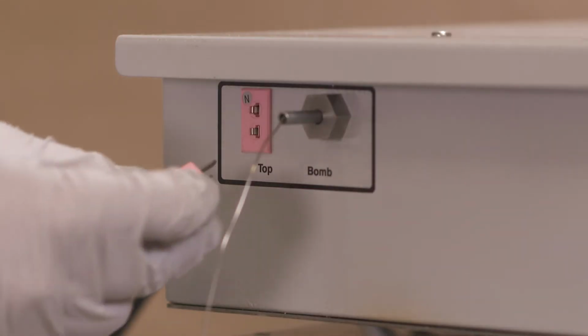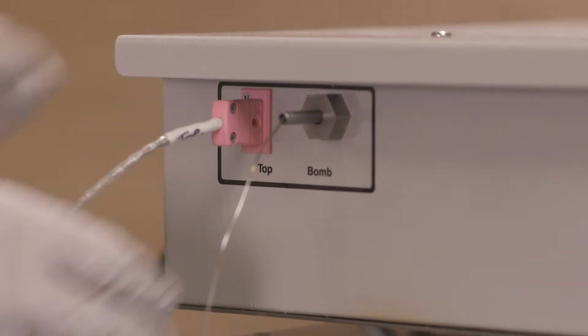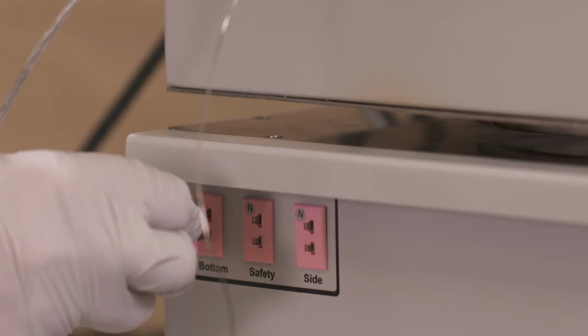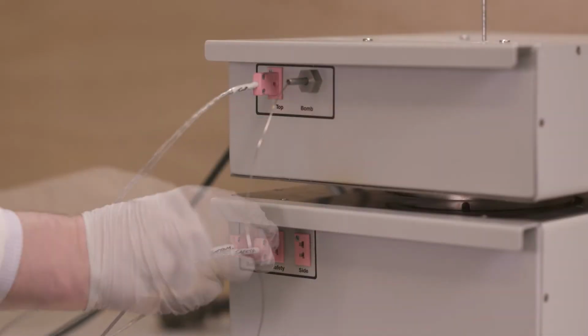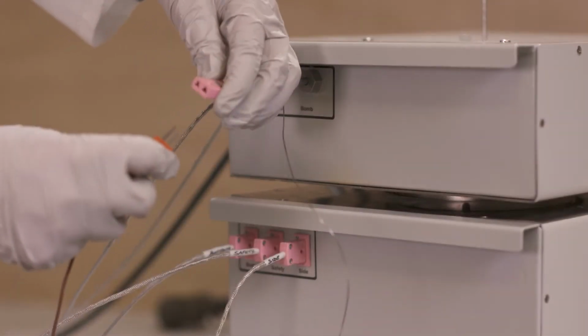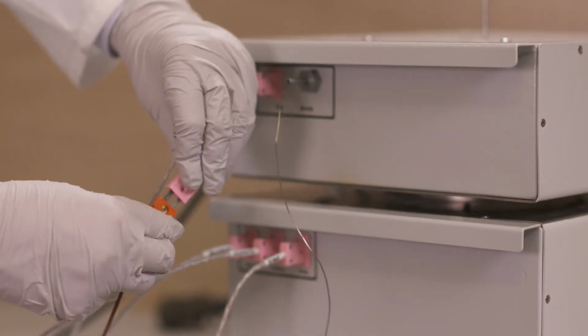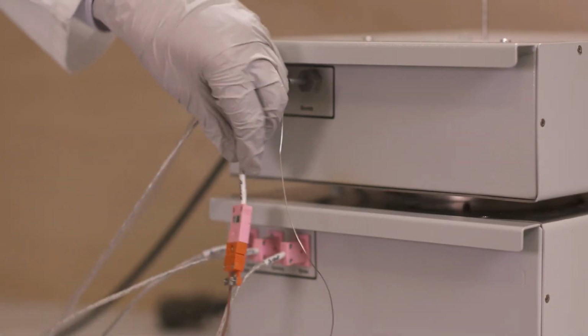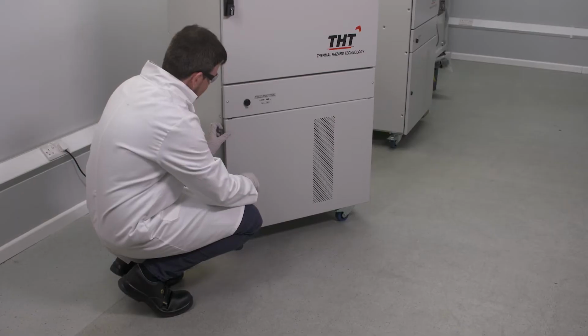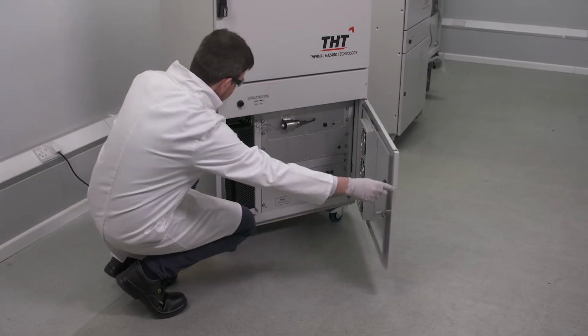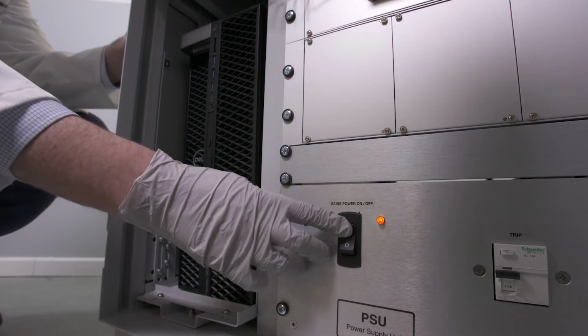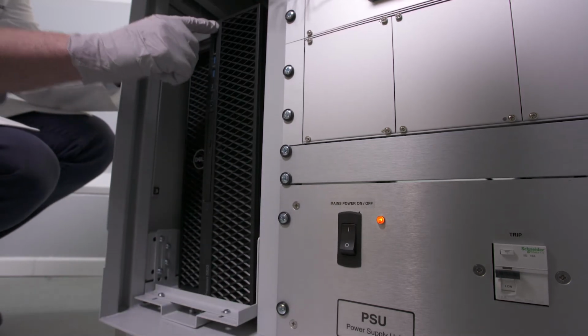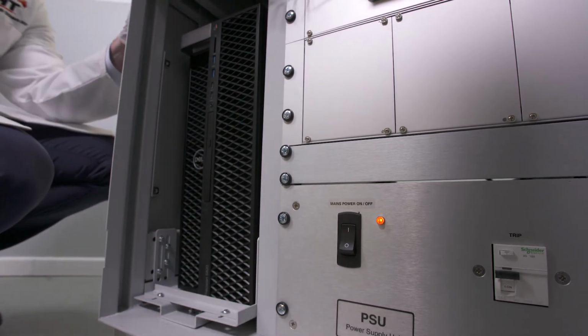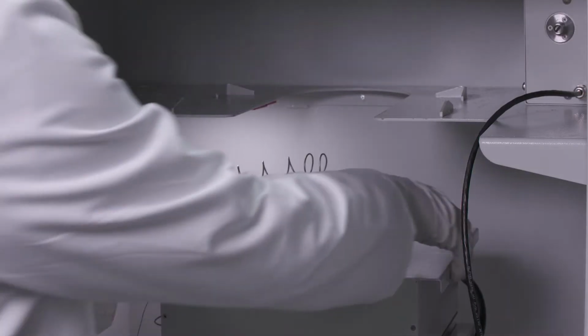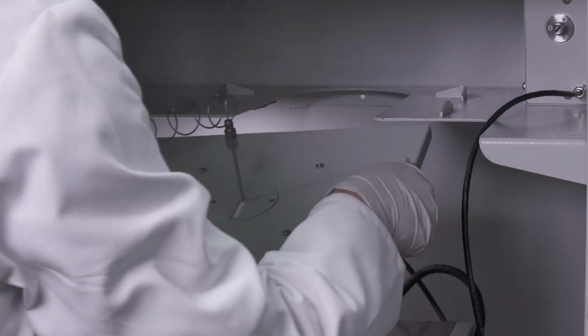On the side of the calorimeter, plug in the 4 labelled thermocouples: top, bottom, safety, and side. Finally, plug the bomb thermocouple connector into its socket. Open the lower door using the key, and turn the power to the unit on using the switch. Power up the PC. Lift the calorimeter lid onto the top shelf. The bomb may be attached underneath, so be careful not to catch it on the calorimeter body.